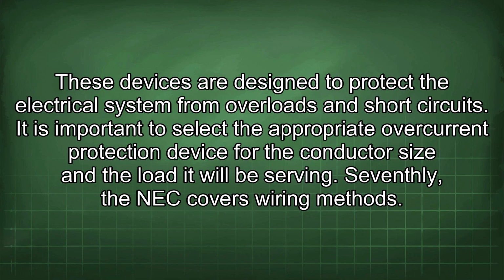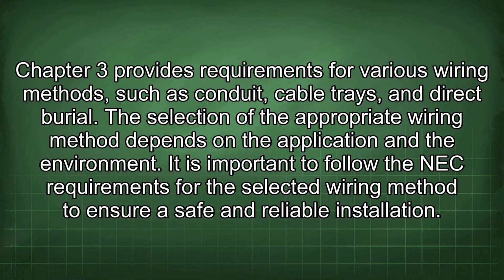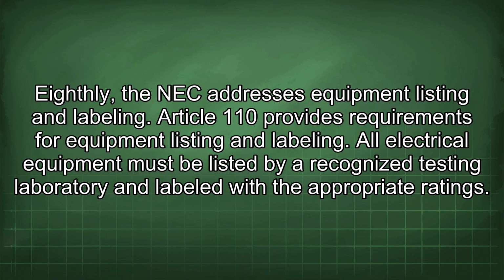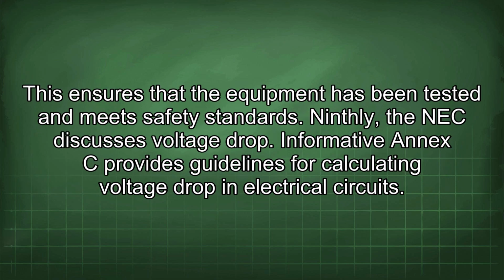Seventhly, the NEC covers wiring methods. Chapter 3 provides requirements for various wiring methods, such as conduit, cable trays, and direct burial. The selection of the appropriate wiring method depends on the application and the environment. It is important to follow the NEC requirements for the selected wiring method to ensure a safe and reliable installation. Eighthly, the NEC addresses equipment listing and labeling. Article 110 provides requirements for equipment listing and labeling. All electrical equipment must be listed by a recognized testing laboratory and labeled with the appropriate ratings. This ensures that the equipment has been tested and meets safety standards.